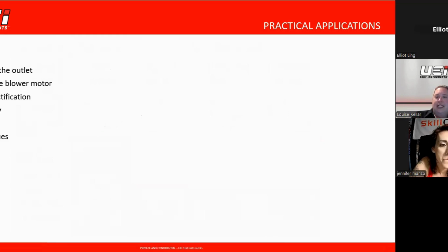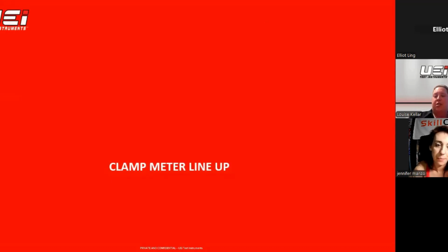And then we have just a lot of our common applications, right? We're going to be testing an outlet, testing a blower motor with it. Flame rectification, in the furnace world that's a huge thing, making sure those aren't dirty and that they're reading properly, so you can do that with the right meter. Continuity, capacitors, board issues, and you can even test some of the gas valves with them. So it's really important to know what your meter can do for you.